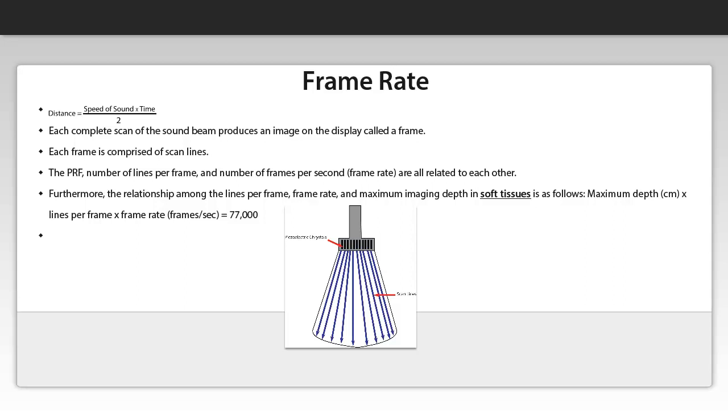The scan lines comprising the ultrasound beam are dependent on the number of piezoelectrical elements in the array transducer that is simultaneously vibrating. Now in order to recall what piezoelectrical elements are and what the array transducers are, please refer back to my previous lecture.